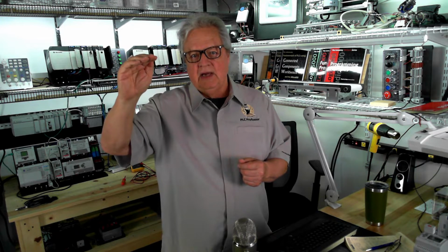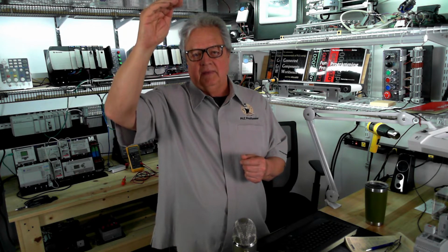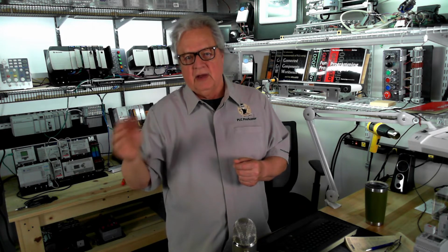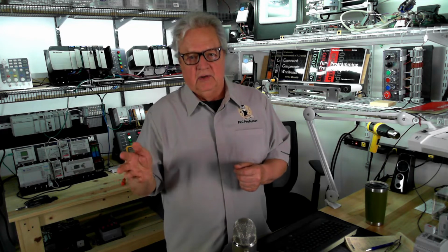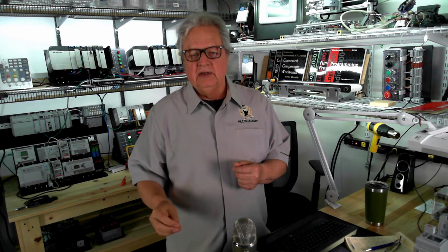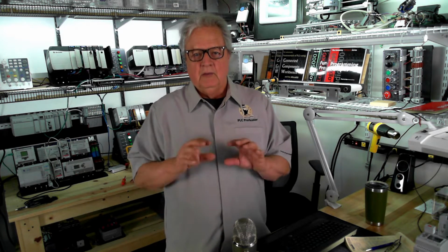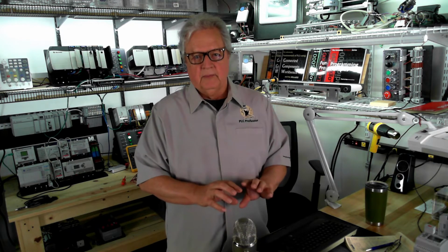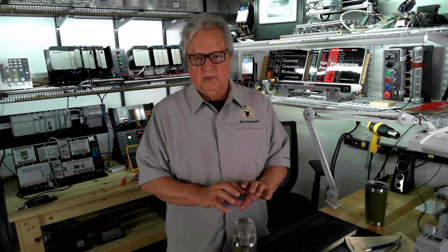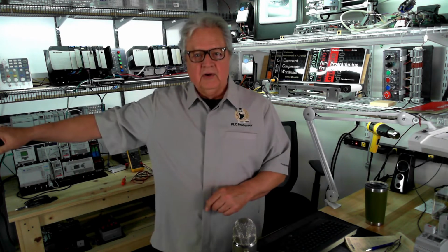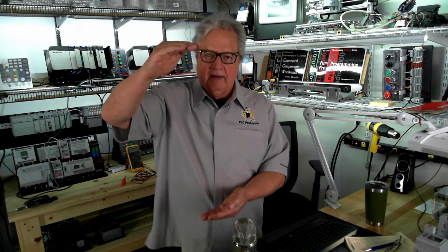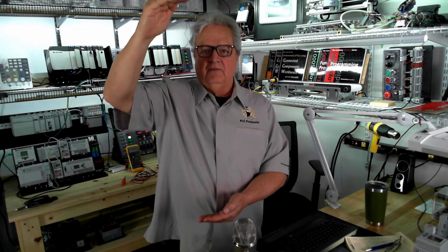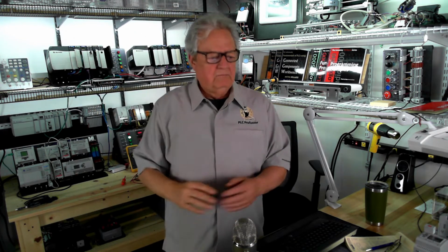Those only get updated on the very first program, and then in the program we don't directly change the state of bits associated with output devices. We change another bit that we created. So all those bits get changed for outputs going down through the program, and when you get to the end, then we copy the state of those global variables that are not output bits over to the real output bits, and out they go to the outputs, which means that the program is totally isolated from any changes in I/O except at the very beginning for inputs and the very end for outputs. Real simple lab project.